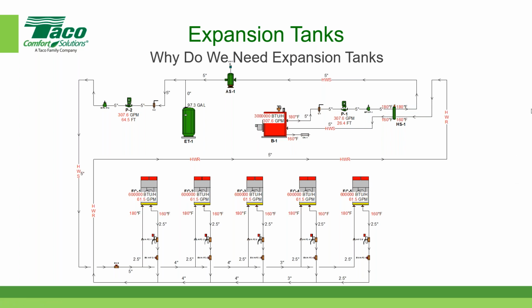So if I could make a little sketch here, sure. If this one needed to be, say, 150 gallons instead of 100 gallons, I'm just making up a number, I could mechanically put in a smaller tank that's 50 gallons. But what if that larger tank should fail? Now I only have 50 gallons, and I run the risk of not having enough expansion volume. So that's why, if I'm going to put in a second tank, I want it to be the same size as the original tank.